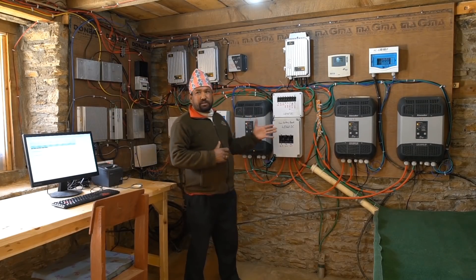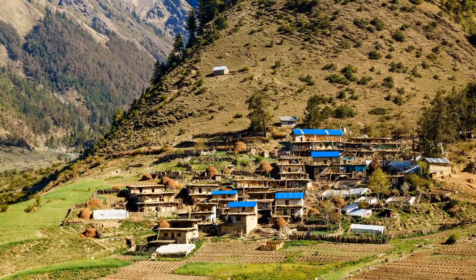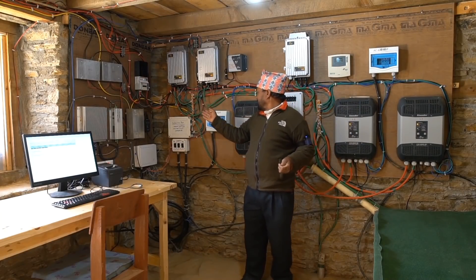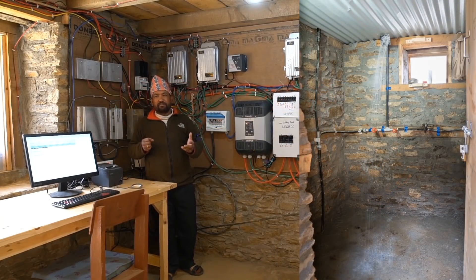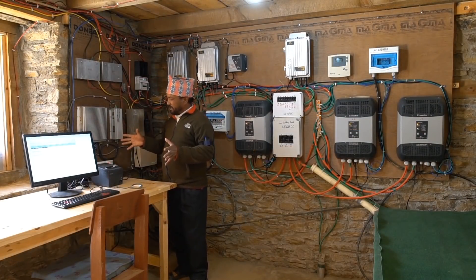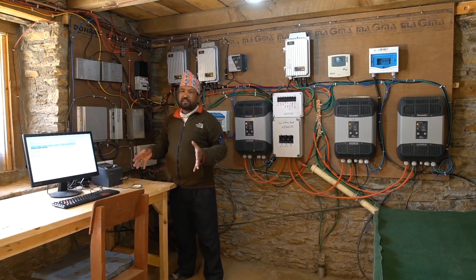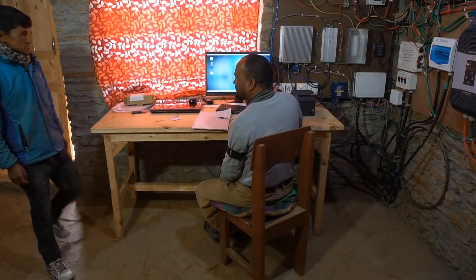For the 230 volt AC electricity distribution line, we consider the village has two parts — one in the east and the other in the west. Electricity transmitted to the western side of the village is controlled with this MCB and the electricity transmitted to the eastern part is controlled with this MCB. In this box is also an MCB that protects the power needed for the water heating system for the shower room, which is one of the various smart dump loads, heating water for personal hygiene for all people working and staying in the community house. The water is heated whenever there is more power available after the village's electricity demands have been met. This PC is in particular for the prepayment pay-as-you-go system — each family pays at the beginning of every new month in advance so that they can have uninterrupted electricity throughout the coming month.